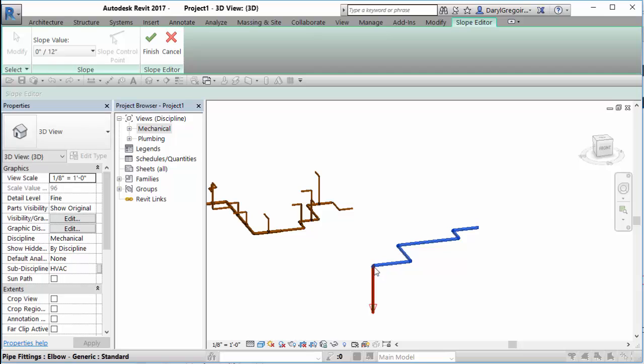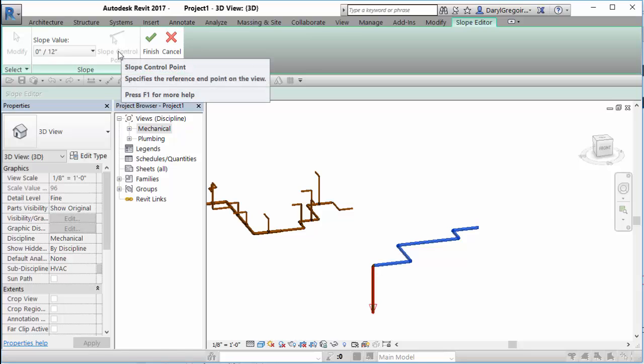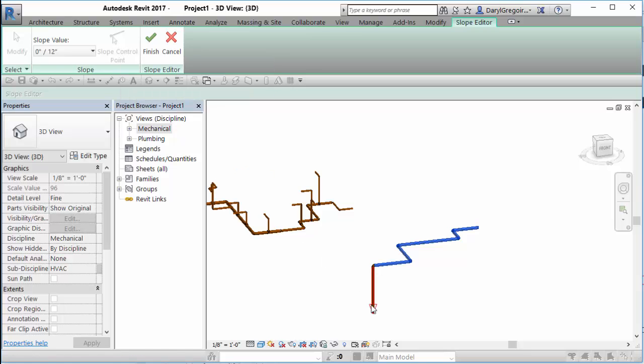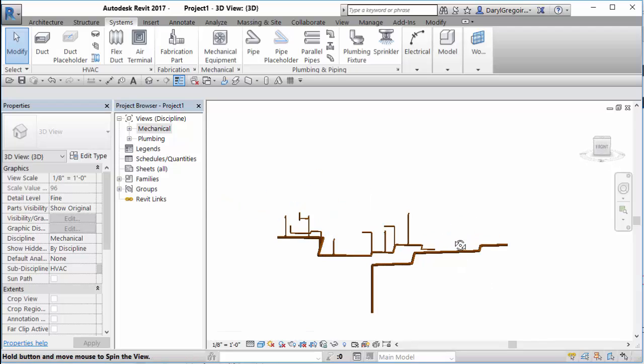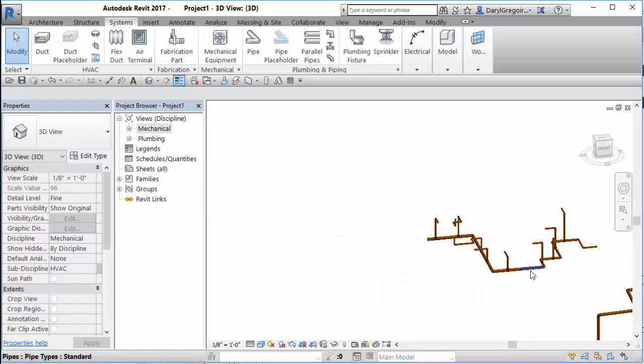Hover, tab, and click to grab those same pipes — but this time there's a vertical stack. Go to slope and now it says this is the fixed point — it is the low point — which means it's going to slope down to there. The other end option disappears because Revit won't assume slope away from a vertical. So hit finish and it slopes down to that drain.